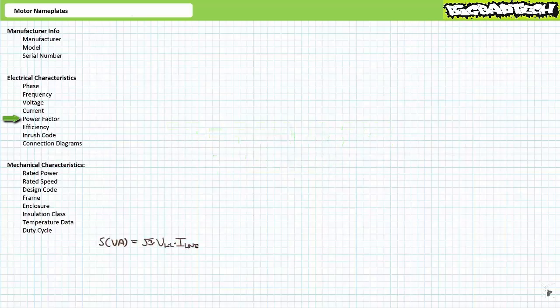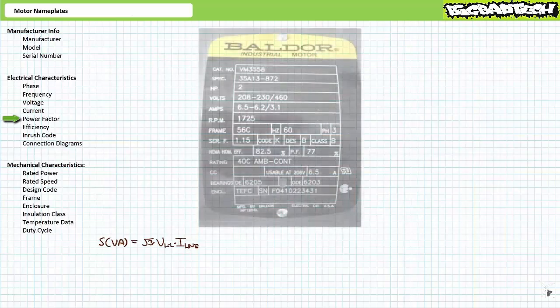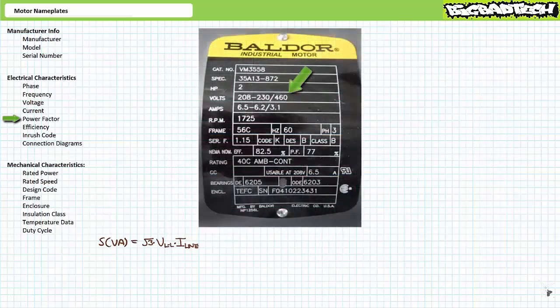Three-phase AC motors are customarily considered balanced loads. Electrical power in a balanced three-phase AC system can be calculated as follows. Apparent power S in units of volt amperes is equal to square root 3 times the line-to-line voltage times the line current. Consider the previous motor nameplate. While in the high voltage configuration and experiencing the rated load, this motor draws 3.1 amps at 460 volts. Square root 3 times 460 volts times 3.1 amps yields roughly 2.5 kilovolt amperes of apparent power.